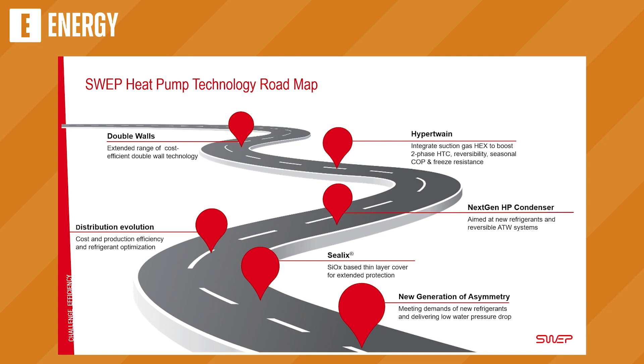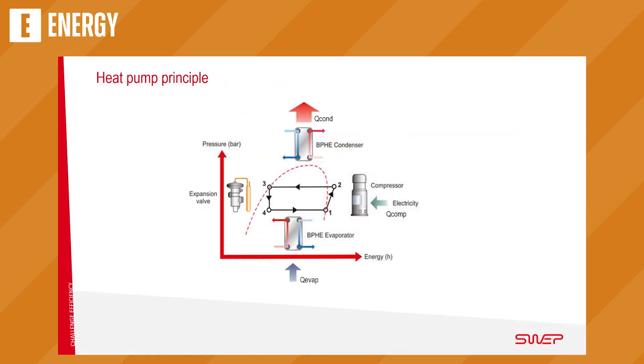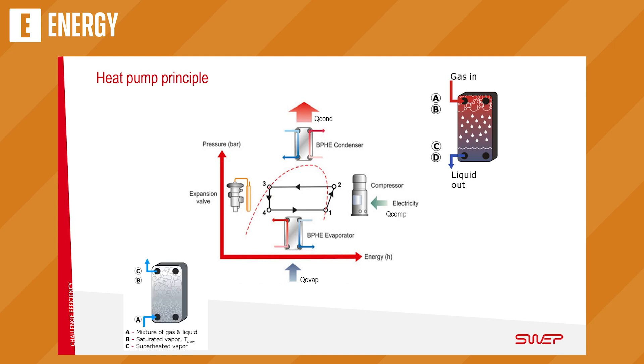This is our heat pump technology roadmap. I will talk about Hypertwain, double walls, next-generation condenser, distribution evolution, Sealix, and a new generation of asymmetric. First, a refresher on the heat pump cycle — it's mainly four components: a compressor, an expansion valve, and two heat exchangers — one condenser and one evaporator. Looking in more detail: the condenser has gas coming in, condensing, leaving heat, and coming out sub-cooled. The evaporator has a mixture of gas and liquid coming in, evaporating, and coming out as gas. That is the heat pump cycle.